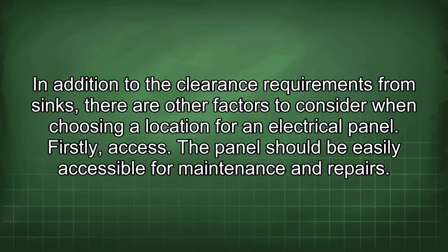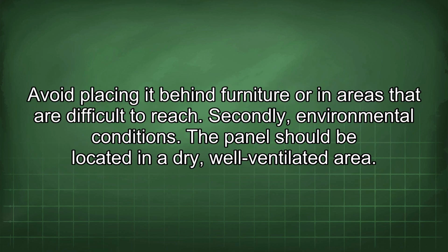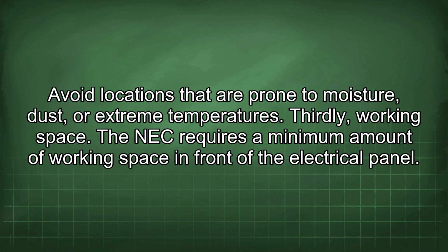In addition to the clearance requirements from sinks, there are other factors to consider when choosing a location for an electrical panel. Firstly, access. The panel should be easily accessible for maintenance and repairs. Avoid placing it behind furniture or in areas that are difficult to reach. Secondly, environmental conditions. The panel should be located in a dry, well-ventilated area. Avoid locations that are prone to moisture, dust, or extreme temperatures.